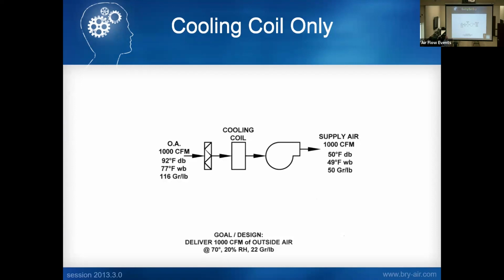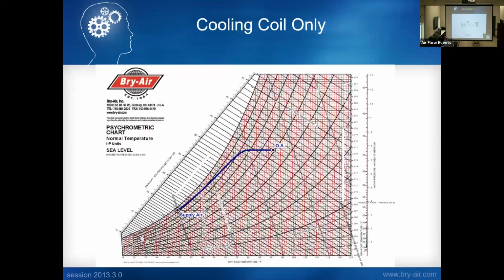Thank you. So here we're going to look at several examples of a system and kind of how we approach our systems. For this example, we're just talking about 1,000 CFM outside air. Our goal was 70 degrees, 20% RH, 22 grains leaving our unit. So we're going to start with the outside air. With the standard traditional DX system, I can get down to about 50 degrees, 50 grains. You can kind of see that on the psych chart.